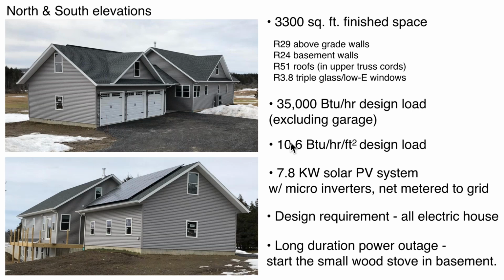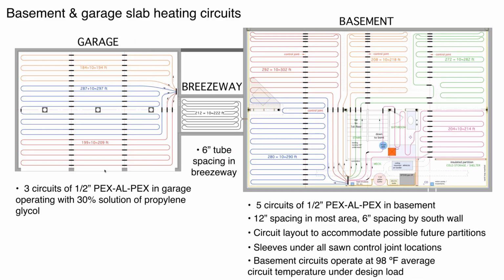Okay, all electric. You probably say, well, what's that chimney? Well, it's a small wood stove. So if there's a long duration power outage, there is a small wood stove in the basement. So that's what the chimney is. Here's the tubing layout plan for the basement. See, all the circuits have been laid out, measured. The black dashes are control joint crossings, so there's a little sleeve over the tubing. All these circuits come back to a manifold down here in the mechanical room.